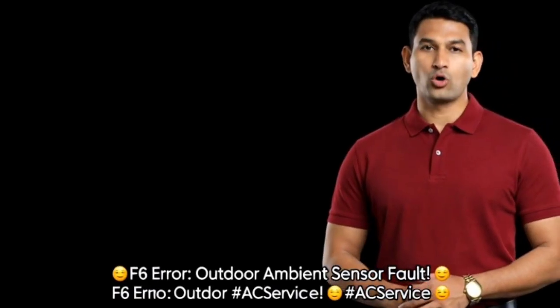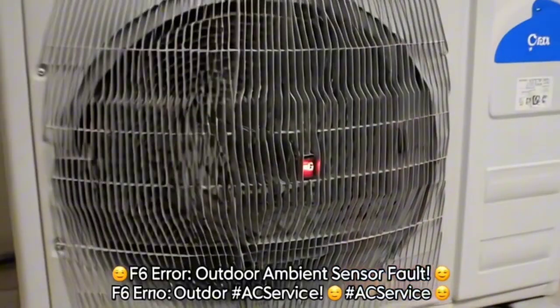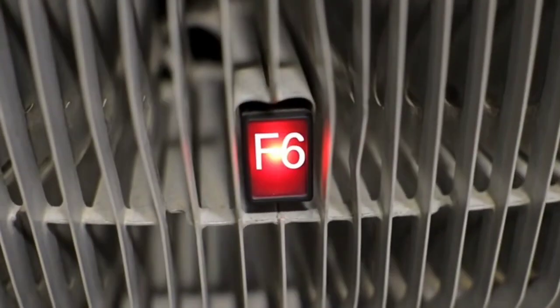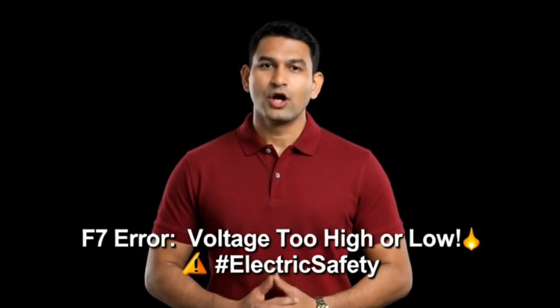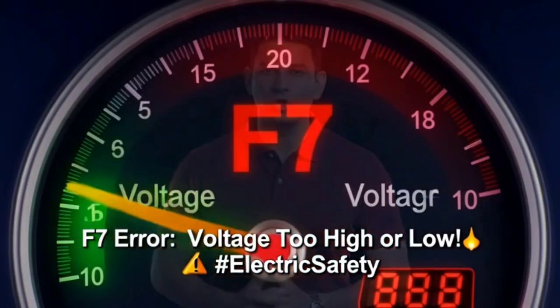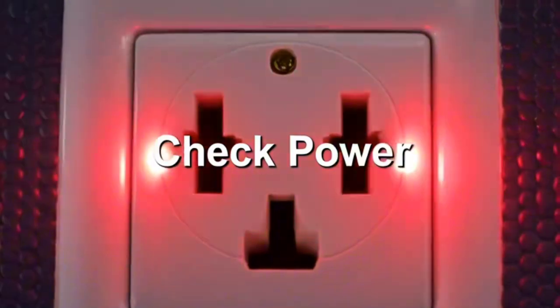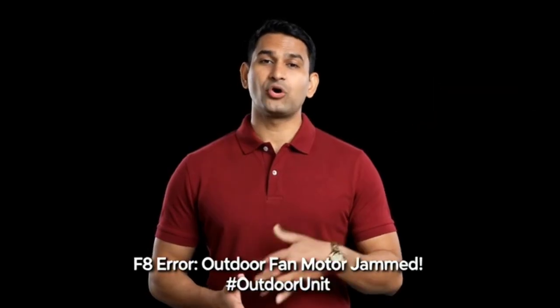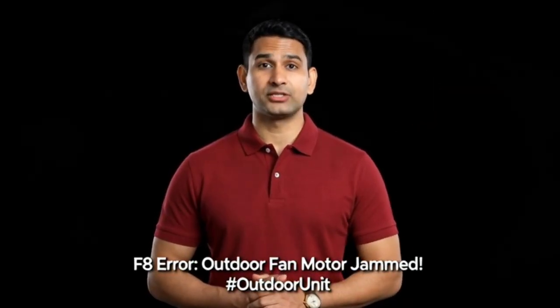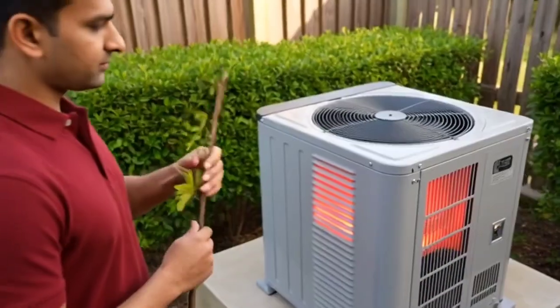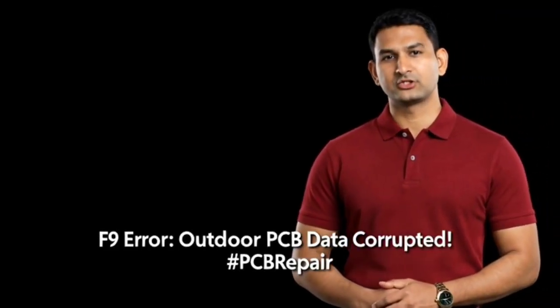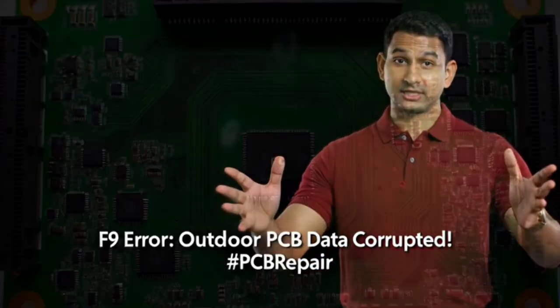F6 means the outdoor ambient temperature sensor has failed. F7 protection. Your input voltage is either too high or too low. F8 means the outdoor fan isn't spinning. Check the motor or capacitor. F9 indicates the memory chip on the outdoor PCB is faulty.